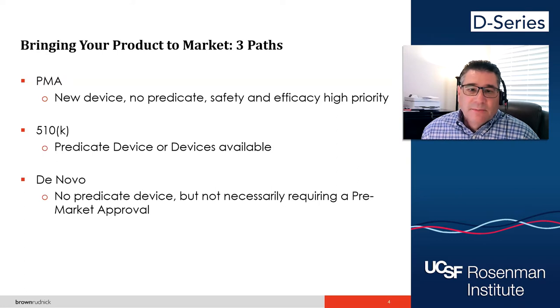Let me just take a minute and go over predicate devices. Predicate devices are basically devices that exist that are similar enough to your product that you can file something called a 510K. It's kind of like making a photocopy, okay? So, in essence, when you have a new device that's implantable or that's of a level three device, and we'll go over the level shortly, you're going to end up in something called a PMA.